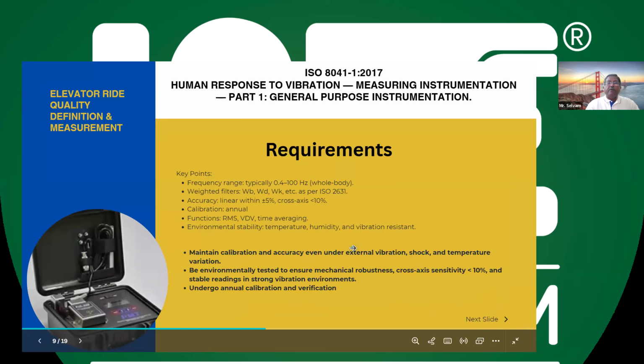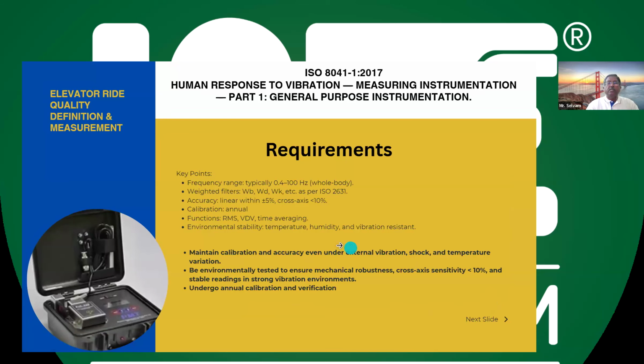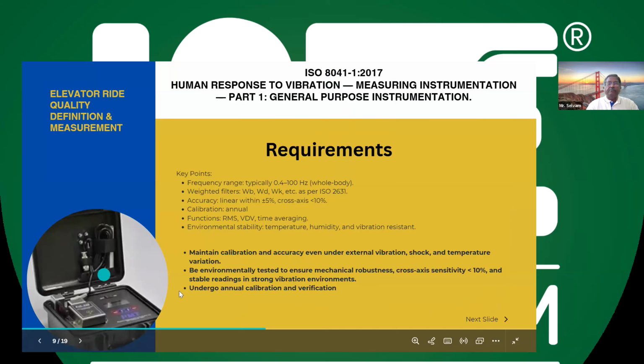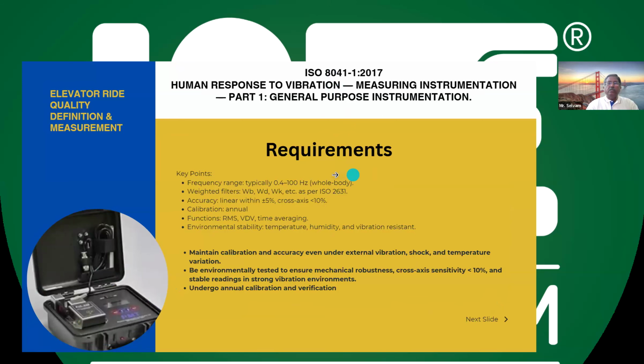So next, apart from ISO 2631, this ride quality standard 8100 is formulated using another standard called ISO 8041. This is meant for the construction of the equipment. Any measuring equipment, how the electronics have to be constructed, how the software has to be designed, and how the accelerometer resolution and sensitivity should be. So these are the aspects governed by this standard.